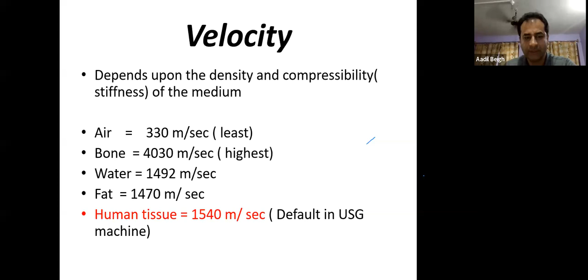That's why artifacts are produced in air when you do a lung ultrasound, because there's the least velocity in the air, in the lungs. The machine assumes the velocity is 1540 meters per second, but the actual velocity is less. In the bones, the actual velocity is the highest, but the machine's default velocity is the same, so that way it produces some artifacts. So the velocity is maximum in bone and least in air. It is denoted by C, and C is equal to the product of wavelength and frequency. C is constant for the USG machine, that means it is 1540 meters per second.